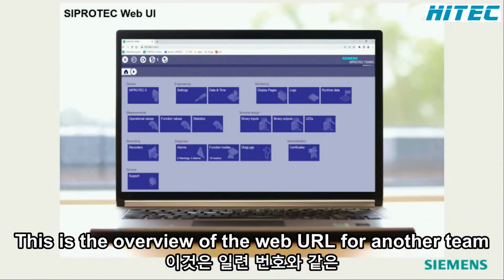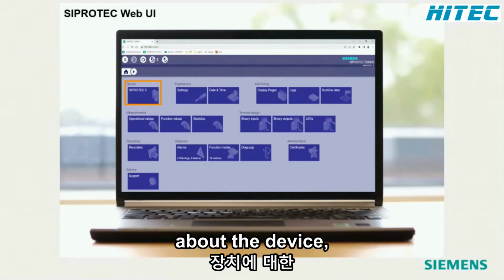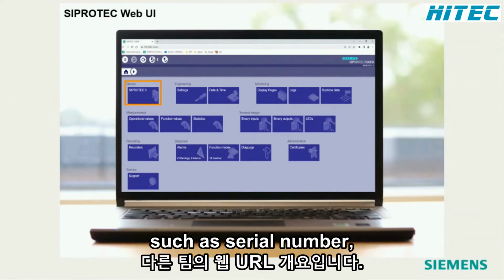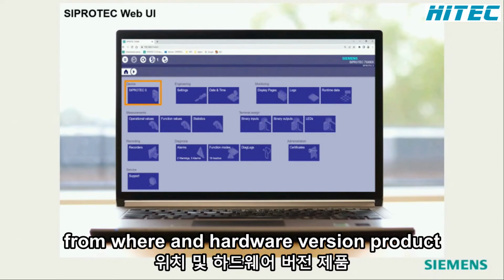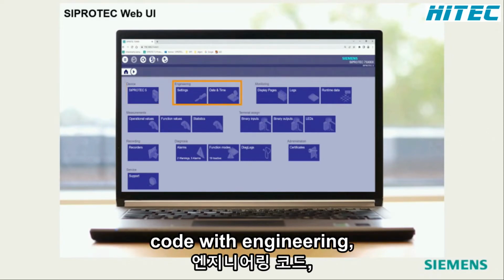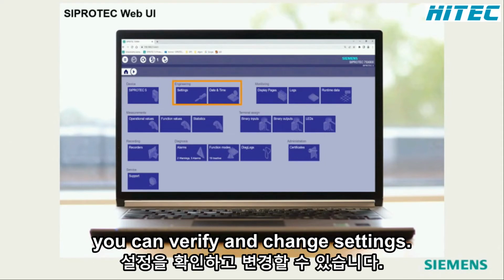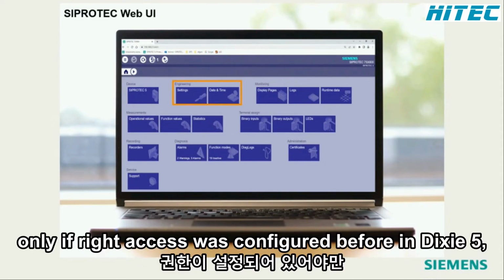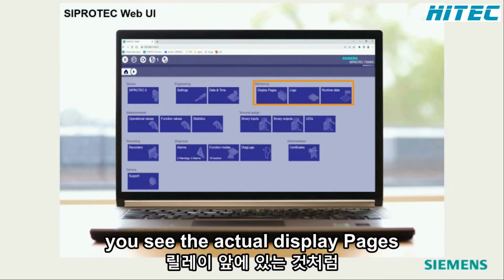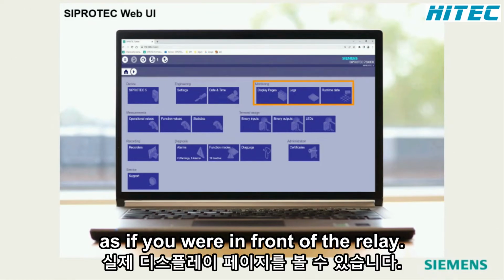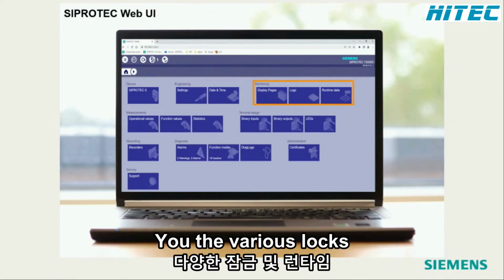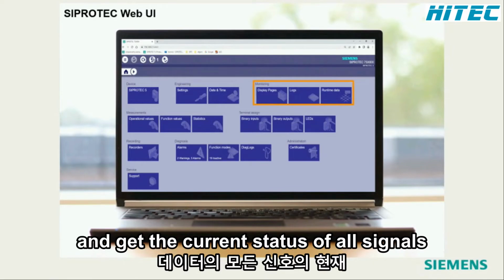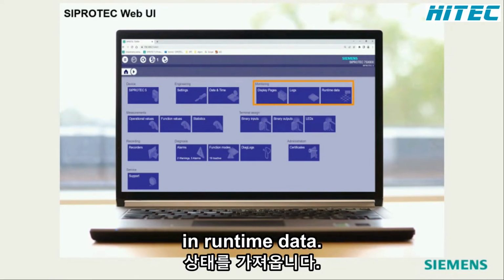This is the overview of the Web UI functionality. Under Device, you get general information about the device, such as serial number, firmware and hardware version, and product code. With Engineering, you can verify and change settings, of course only if write access was configured before in DIGSI 5. Under Monitoring, you see the actual display pages as if you were in front of the relay. View the various logs and get the current status of all signals in runtime data.